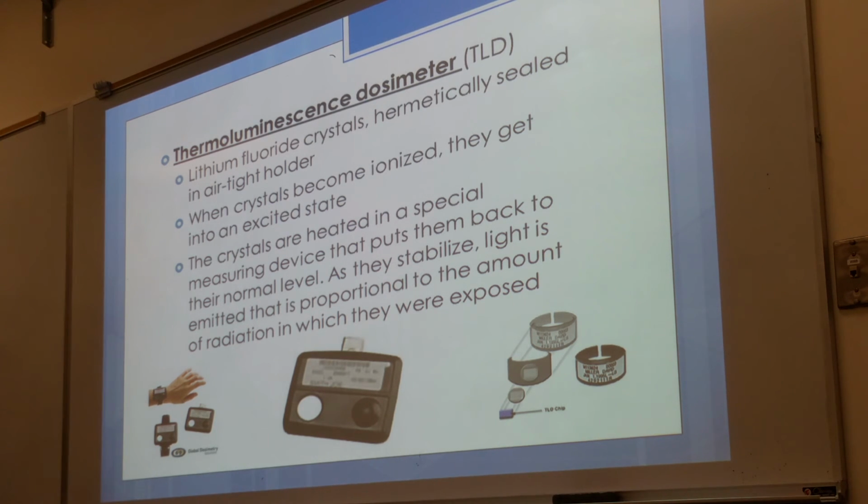So we're going to send the badges, every 3 or 4 months, to the issuer. The crystals are going to be heated in a special measuring device that puts them back to their normal level. As they return back to their normal state, light is emitted that is proportional to the amount of radiation it received. Got it? Let's go on to the next.